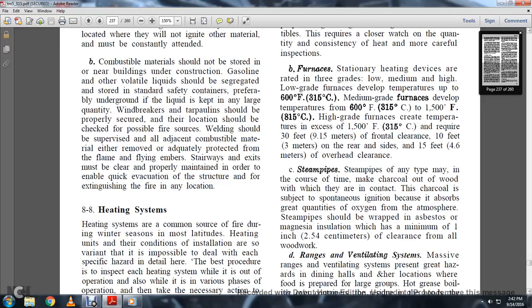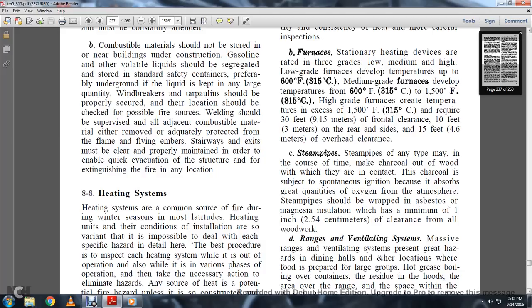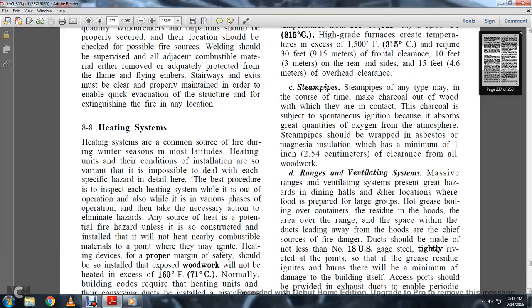the overhead clearance. Steam pipes, in the course of time, make charcoal out of the wood which may be in contact with them. The charcoal is subject to spontaneous ignition because it absorbs greater quantities of oxygen from the atmosphere. Steam pipes should be wrapped in asbestos or magnesia insulation, which will maintain a minimum of 1 inch of clearance from all woodwork.